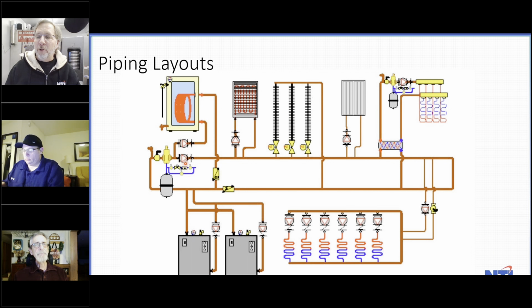Right. This pump would go off, using I would assume a 262 tekmar control at the time. This pump goes off when this pump comes on, so that this doesn't heat up the rest of the house. Too many people in my day were putting the indirect water heaters way down here at the end of this loop, which means this whole loop is hot all the time, which is defeating the purpose. So here we have it right here. It's the first thing off and the last thing back, so that only this area is getting the heat during the summer. This is just a phenomenal design, Ted. I love this. I saw this and I got so excited. I changed it to a JPEG and blew it up so we could talk about it, you know?